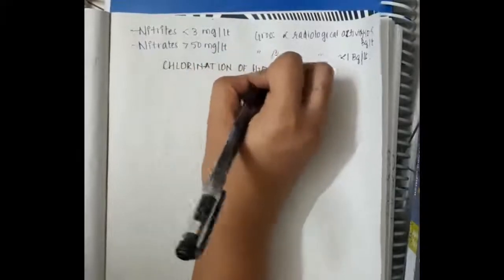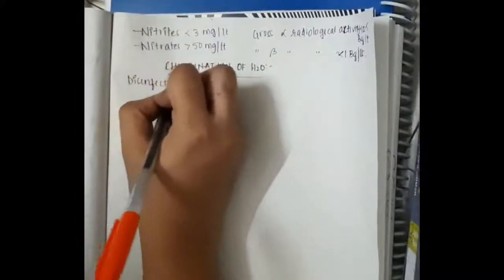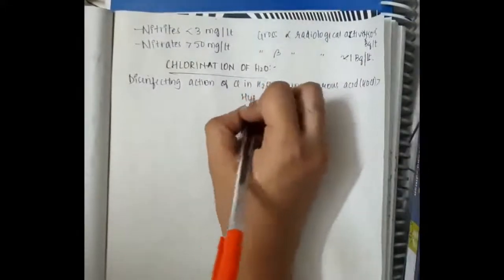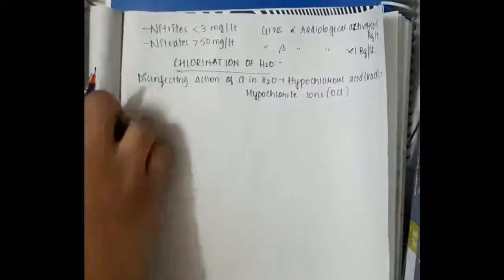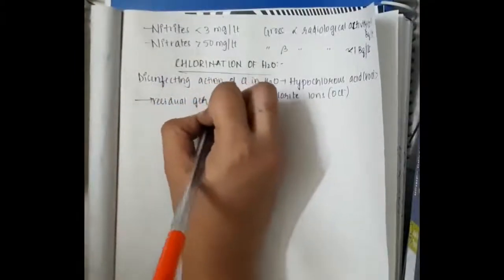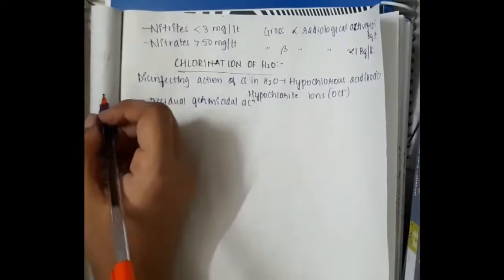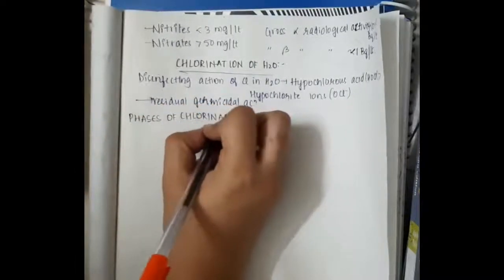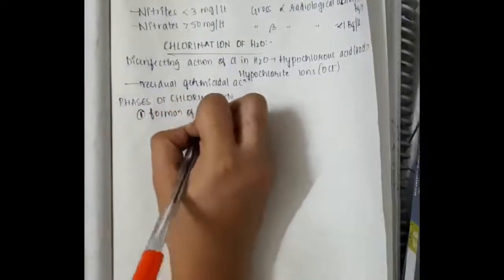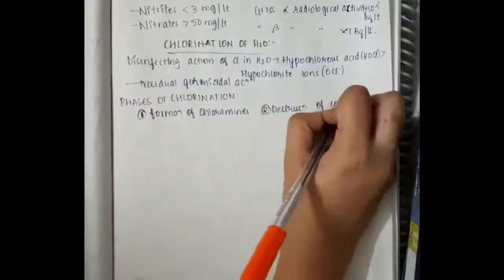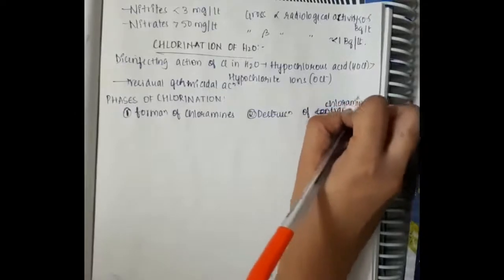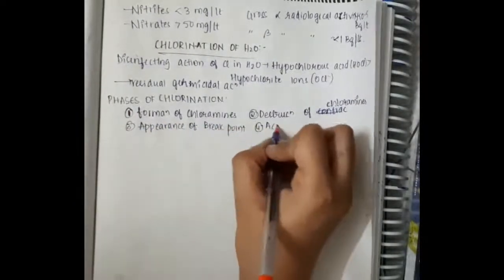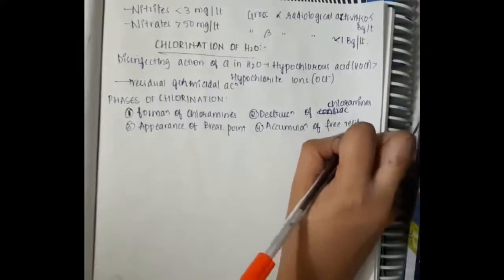Let us learn some points about chlorination of water. Chlorination of water is the disinfecting action of chlorine in water — that is hypochlorous acid more than hypochlorite ions. In disinfection of water with chlorine we use hypochlorous acid mostly, and this has residual germicidal action. The phases of chlorination include: first, formation of chloramines; second, destruction of chloramines; third, appearance of break point; and fourth, accumulation of free residual chlorine.